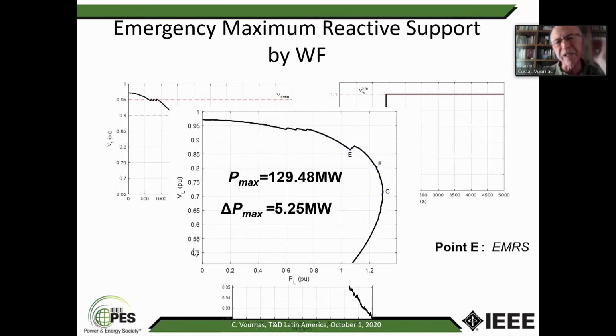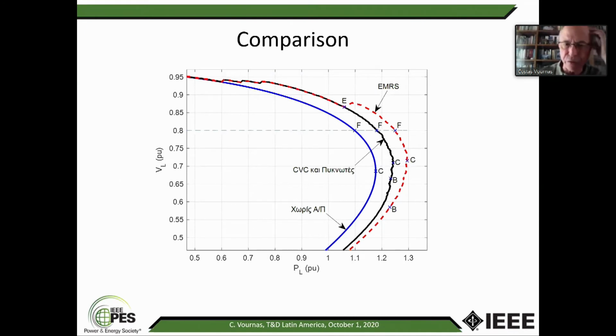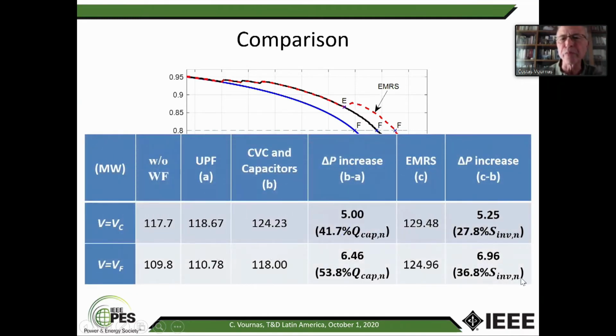So if I go again on the PV, load power versus load voltage, you see I increased by another 5 megawatts from what I did using the capacitors and the constant voltage control. And also you see how the point F comes closer to the point C, which is the maximum power versus the low voltage limit. So this is for this simple system, and you can see all the 3 curves together: no wind farm, sorry for the Greek, unity power, constant voltage and capacitors, and on top of this, the EMRS, which starts changing after this point E. So you see that there is quite some room for improvement.